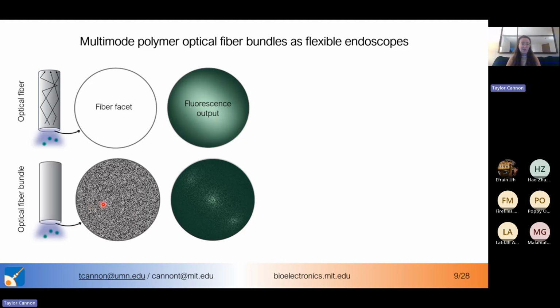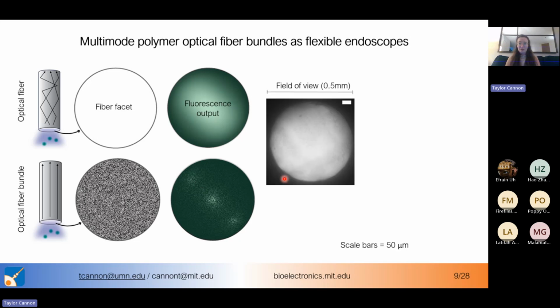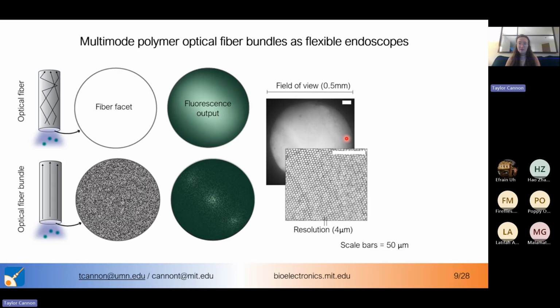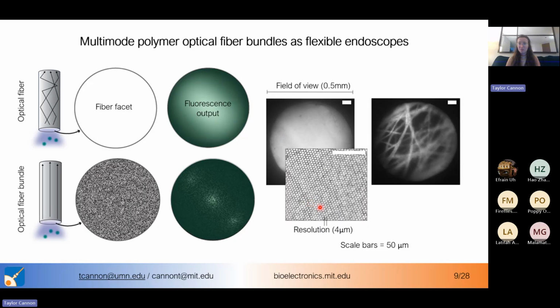Each of these individually arrayed waveguide cores is able to independently transmit that fluorescence information and then give us this somewhat pixelated but still discretely resolved fluorescence output. So here's an example of what some of these devices look like, where important parameters to note would be that your field of view is going to be dependent on the diameter of the fiber bundle. The resolution is going to be dependent on the individual size of these fiber cores.